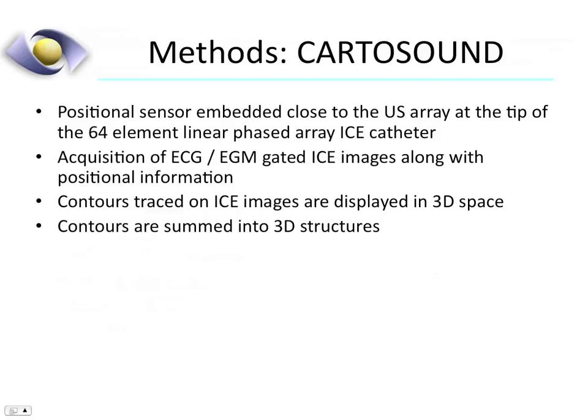This brings us to CartoSound technology. CartoSound involves the use of an intracardiac echo catheter with a positional sensor embedded close to the ultrasound array, whereby one can acquire ECG or electrogram-gated intracardiac echo images along with positional information for each image. Contours traced on intracardiac echo images are then displayed in 3D space and summed into 3D structures.